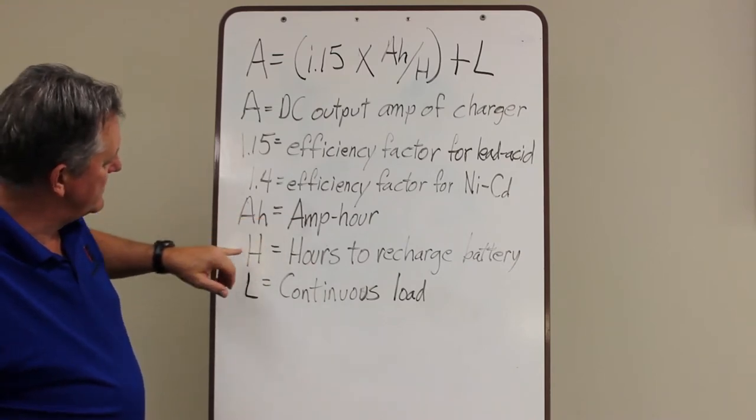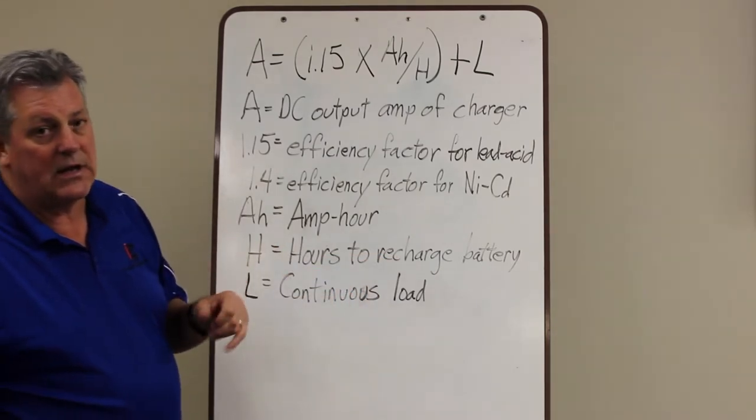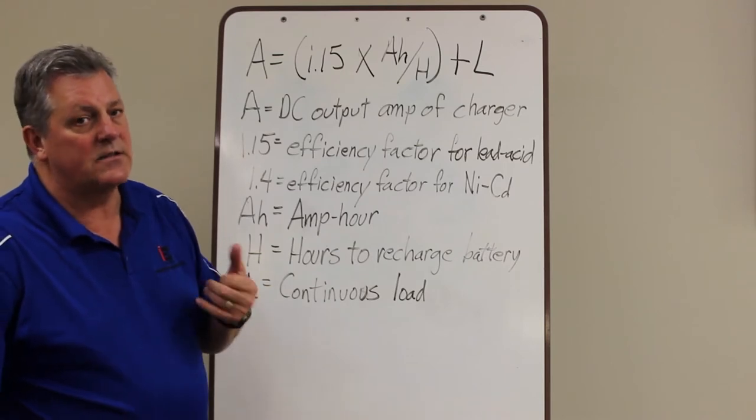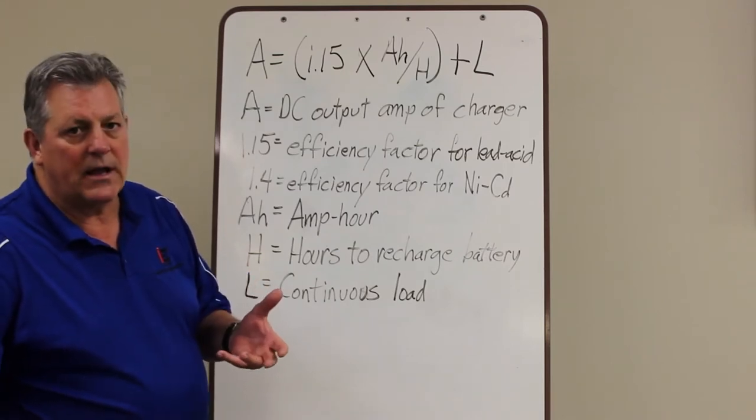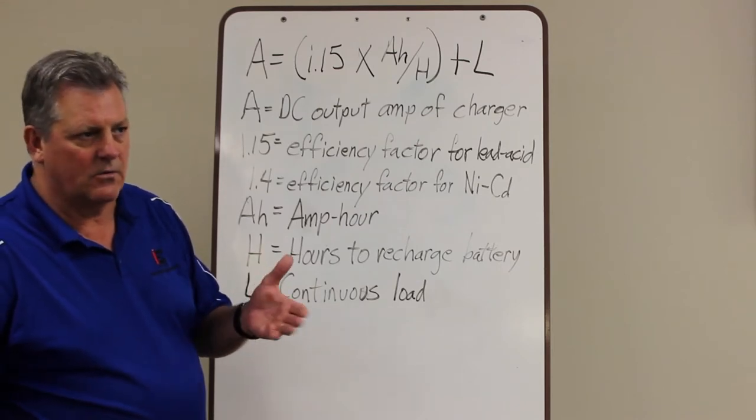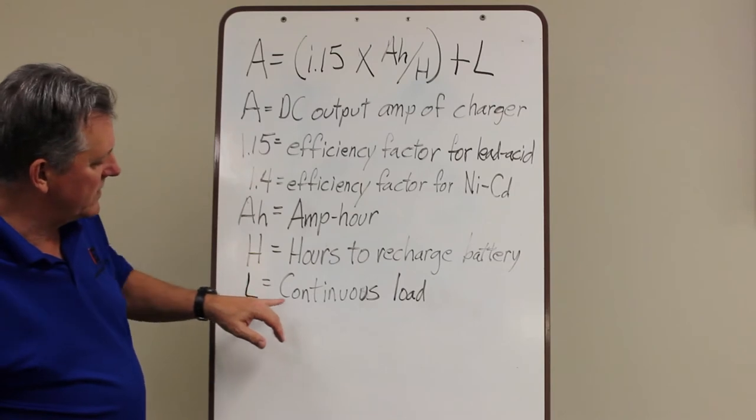AH means amp hours. H is hours to recharge the battery and that can be anywhere from 8 to 24. I've seen as many as 48 but generally they run at 8. That's the minimum. You can't charge a lead acid battery any faster than 8 hours. It's a chemical reaction so we work with 8 hours as a minimum. And then L would be the continuous load.